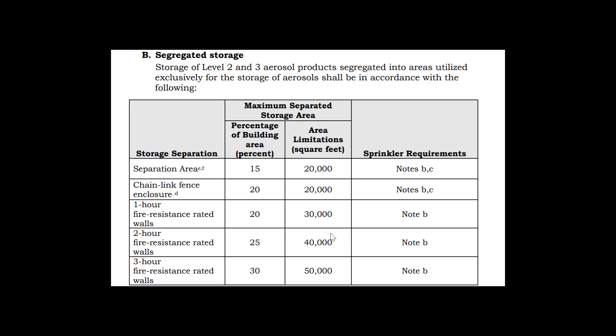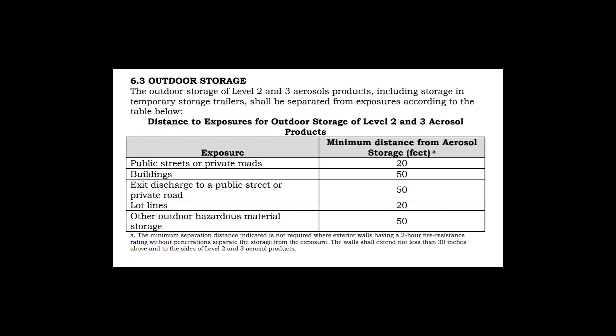Segregated storage separation is extremely important. We will review the chain link fence, 1-hour fire-resistant rated walls, 2-hour fire-resistant rated walls, and 3-hour fire-resistant rated walls. For outdoor storage of Level 2 and Level 3 aerosol products: public streets and private roads need to be at least 20 feet minimum distance; buildings a minimum of 50 feet; exit discharge to a public street or private road at least 50 feet; lot lines at least 20 feet minimum; and other outdoor hazardous material storage areas need to be at least 50 feet.